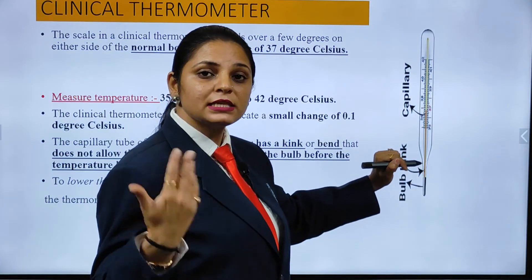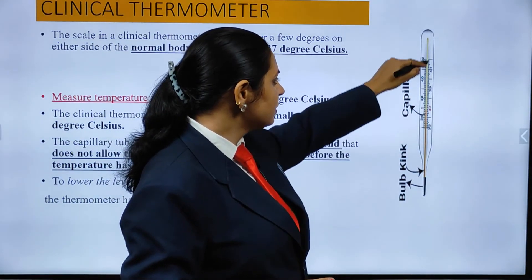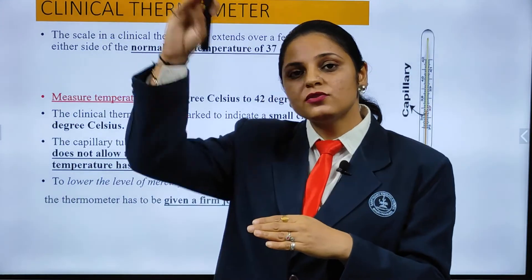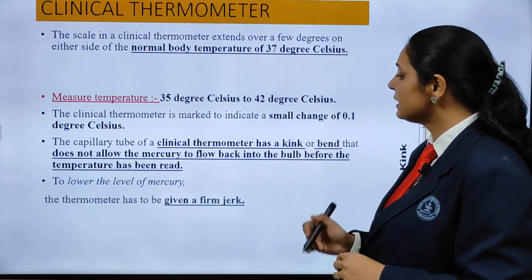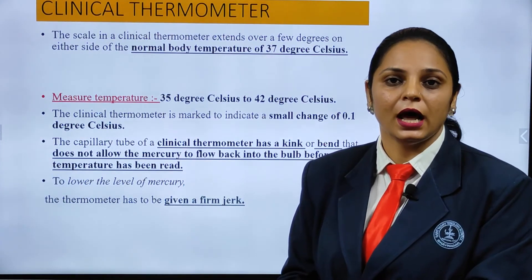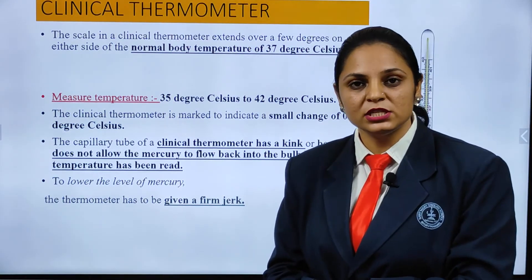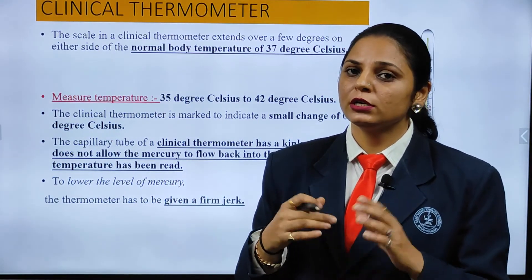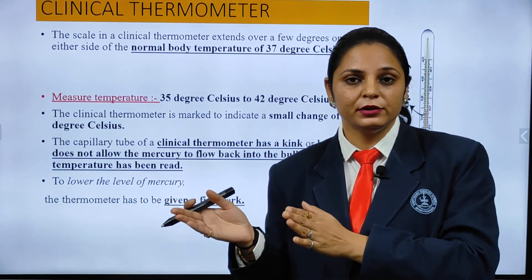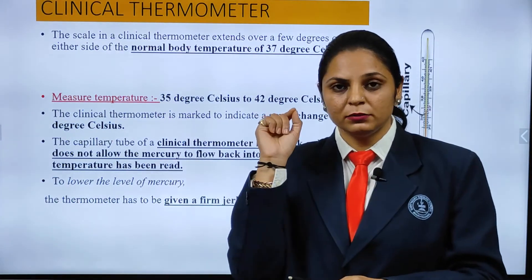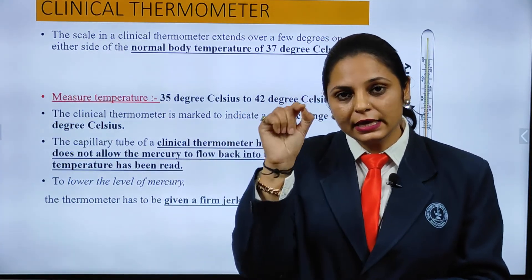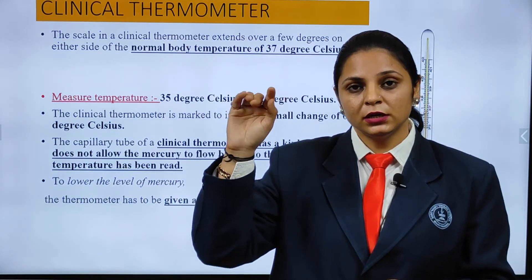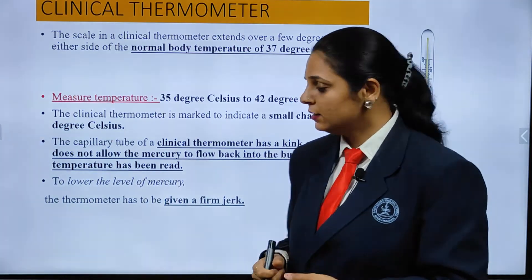As mercury gets heated, it rises in the capillary tube. The clinical thermometer has a kink — a bent constriction — which does not allow the mercury to fall back down when you take the thermometer out. This is compared with the laboratory thermometer, which has no kink. If the kink is not present, the temperature reading for a particular point would drop down immediately and we would not be able to record it.